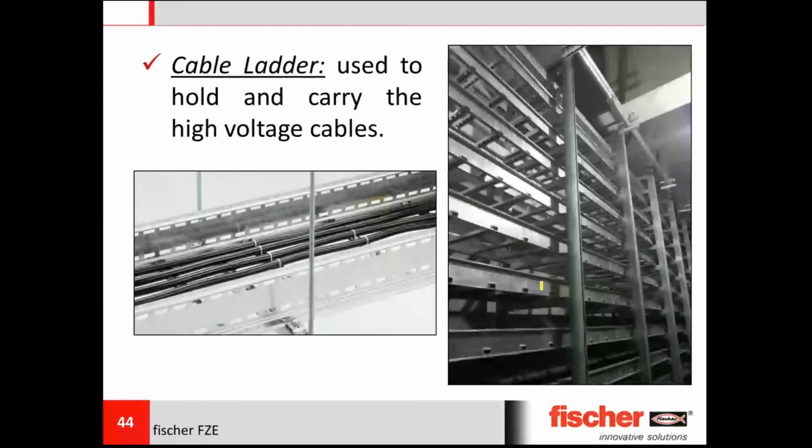Any electrical contractor here? Any electrical engineers? Okay, so the answer is there obviously in the picture. Cable ladders are mainly used to carry high voltage cables which are heavier and which cannot be carried in a cable tray because the load itself is much higher. So we not only design a single cable ladder, we sometimes provide a rack solution as you can see on the right picture.